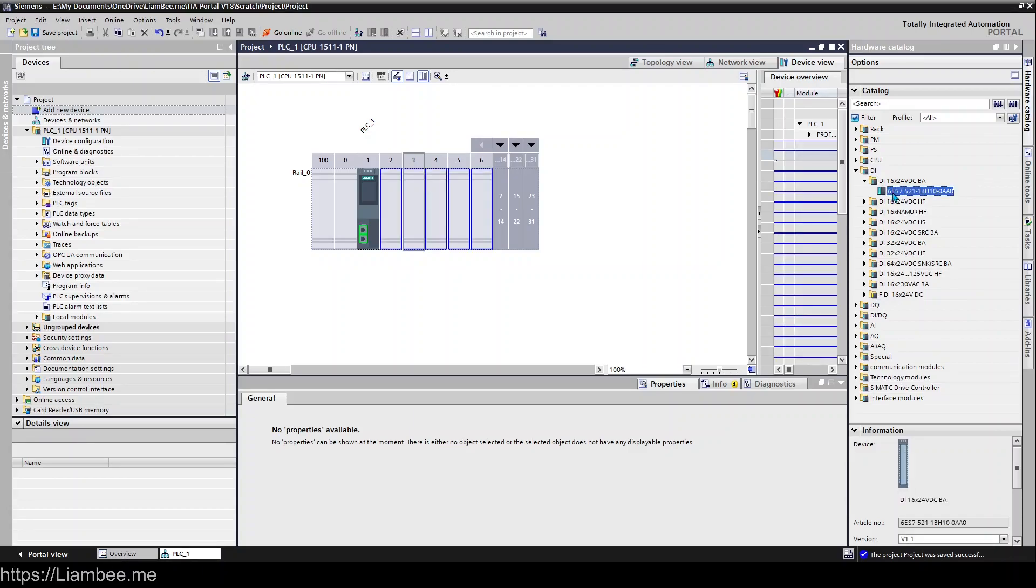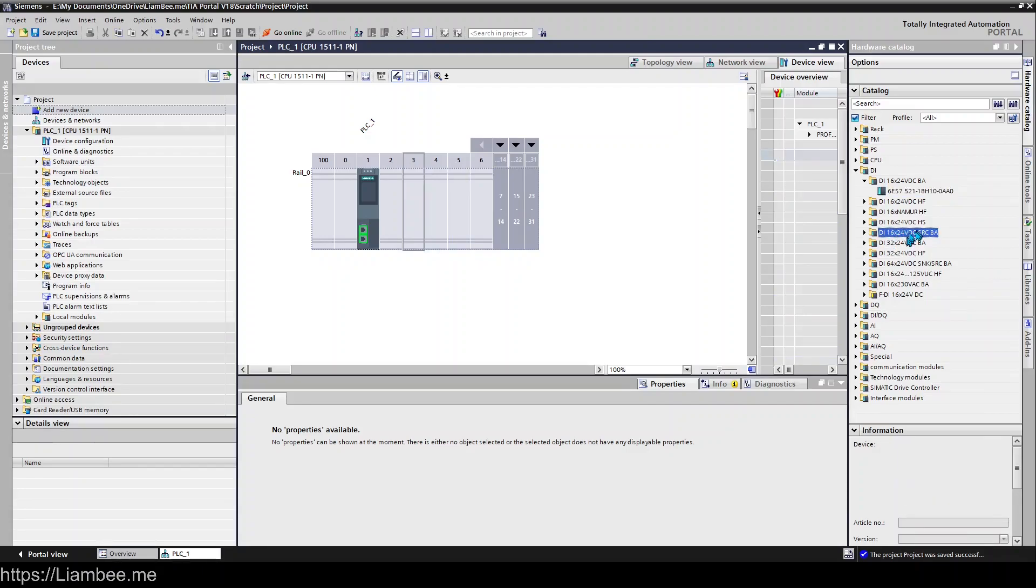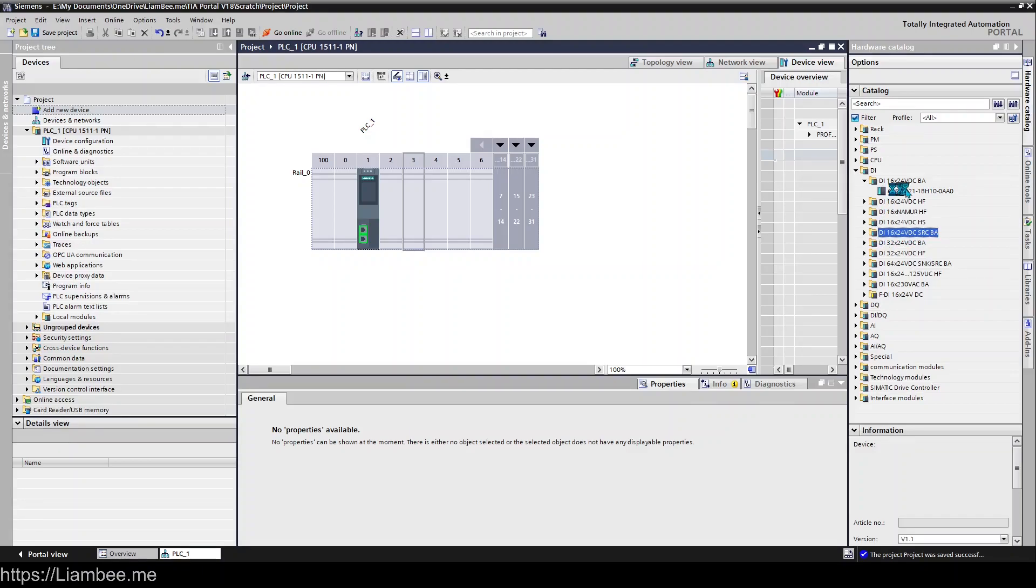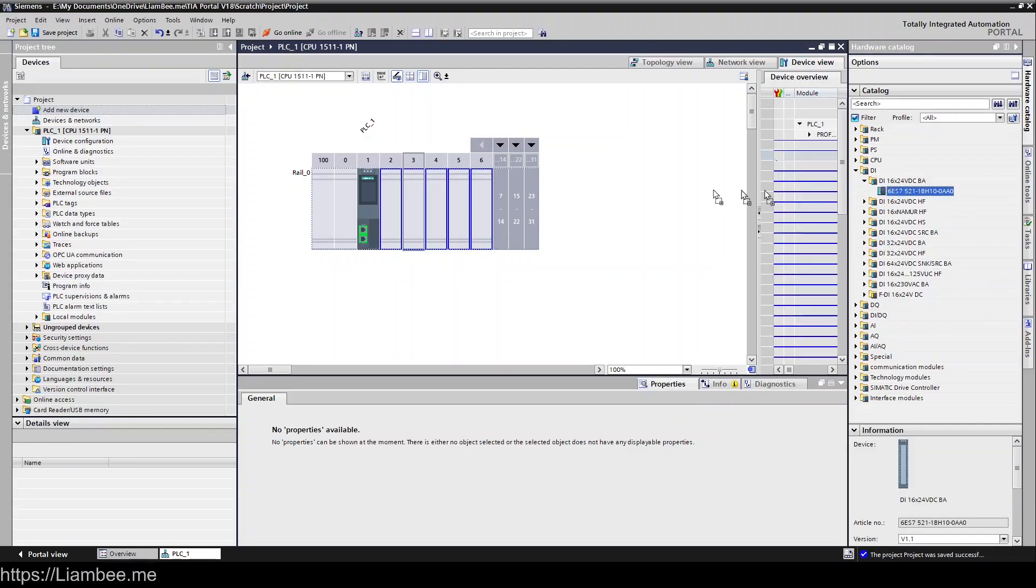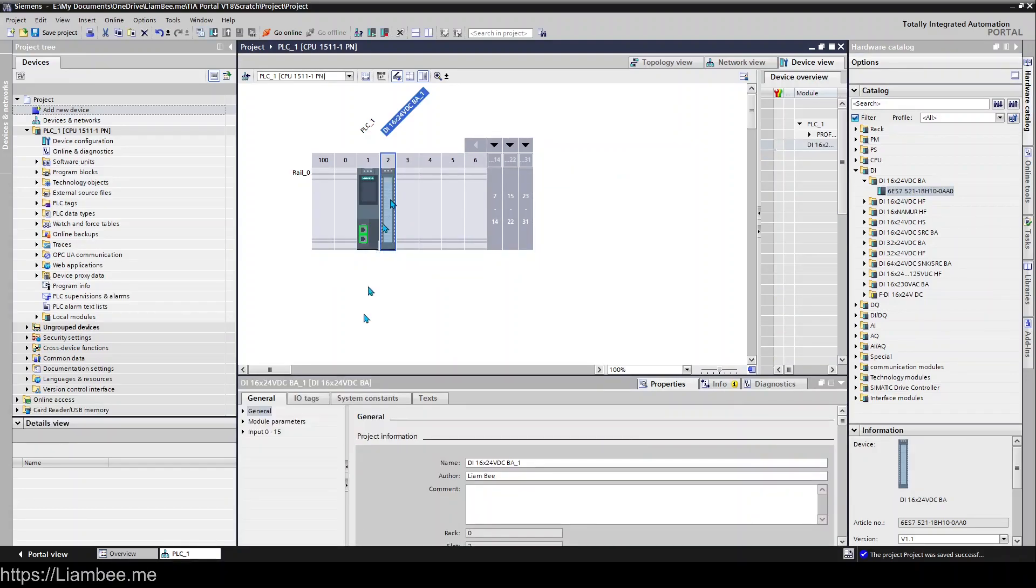You can refer to the documentation for each of these to find out what the specific differences are. Some of them are high frequency, some of them are 64 channel rather than 32 or 16. They are in the name here as well, so this one's a 16-way 24 volt digital input card. If we go ahead and drag this one in, you can see it simply appears and then all of its properties appear down here.